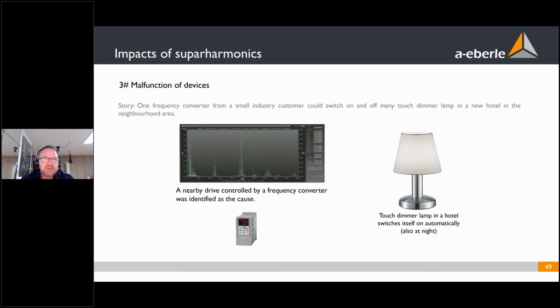And the next problem, sure, the biggest problem, is malfunctions of different devices. In one also nice story, a big hotel installed touch dimmer lamps in all rooms. So you only touch the lamp and you can switch your light on and off. In this low voltage grid, a small industry customer is producing some disturbances with a frequency converter. The multiples of the disturbances have exactly the frequency the touch dimmer lamp is working at in this low voltage grid. And the production company was producing daytime and nighttime on all working days, not on the weekend. But even during the nighttime, the industry customer was switching the lamps in the hotel on and off automatically. So nobody can sleep here.